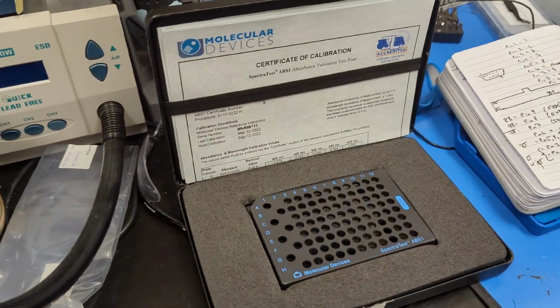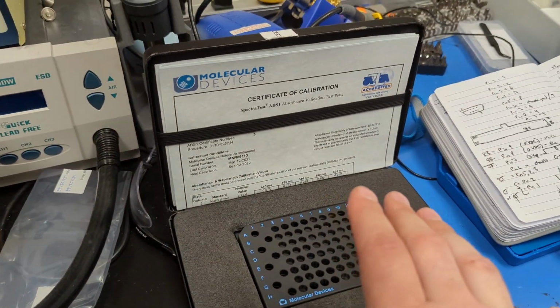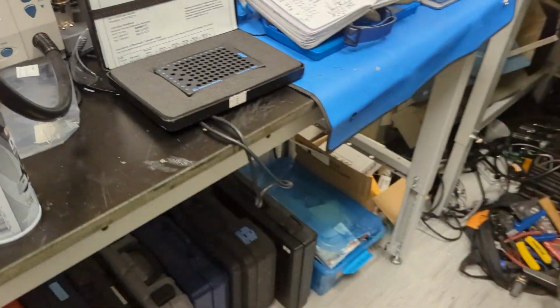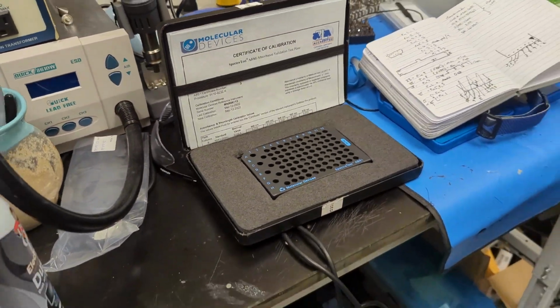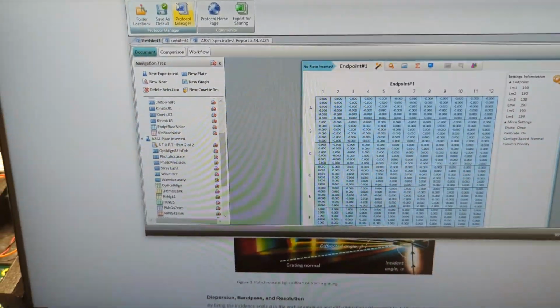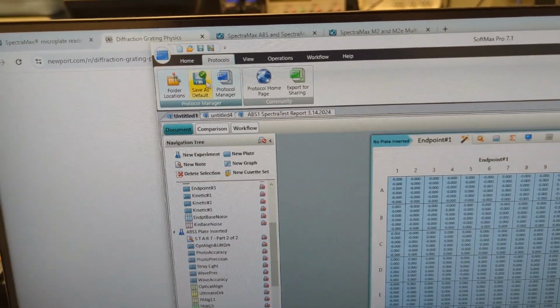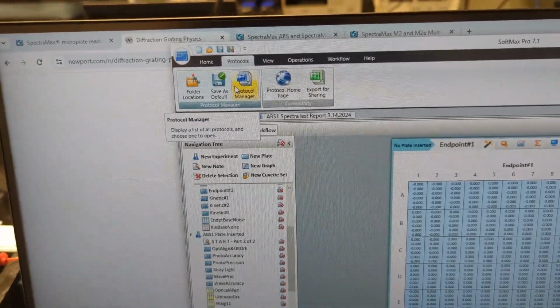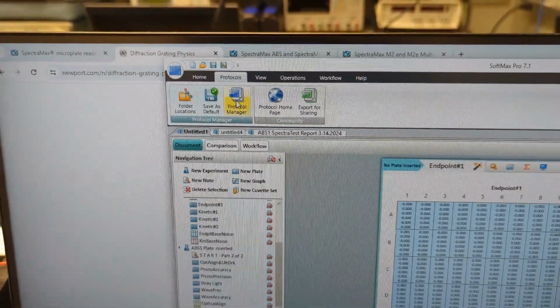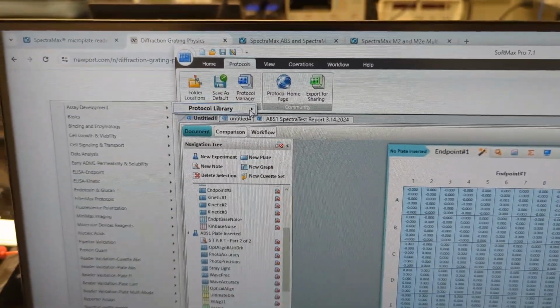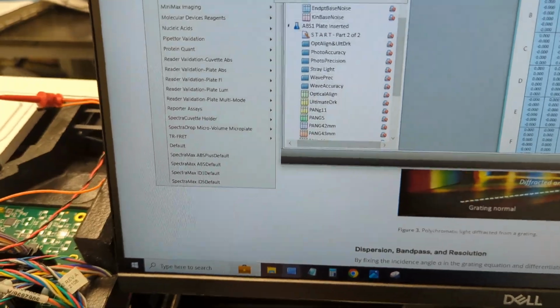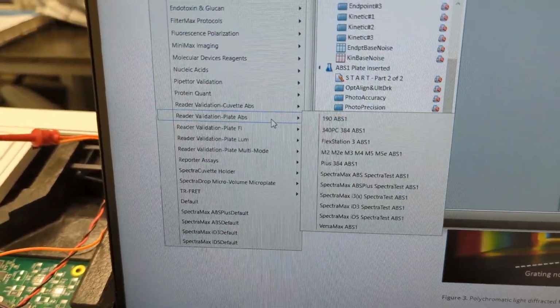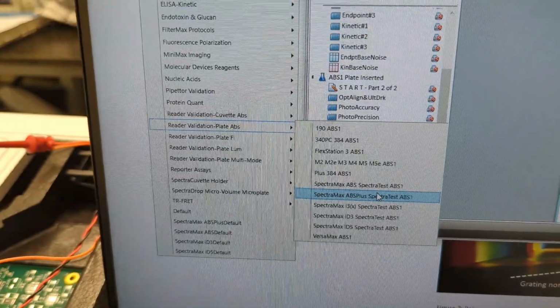But yeah, you're going to need one of these for the wavelength accuracy standards. Without any help from the manufacturer and this, it's going to make doing this very difficult, at least I think. But with that plate, there's one cool thing about this software: it does make doing the calibration verification very easy. So if you go to Protocol Manager in the SoftMax Pro software, and go down to reader validation plate absorbance, you pick the SpectraMax ABS Plus, if that's what you have. That's what I'm in right now.